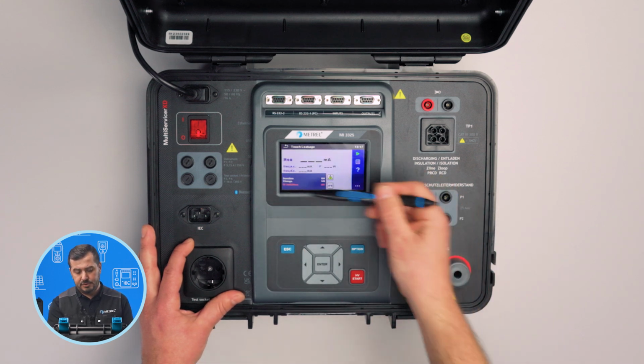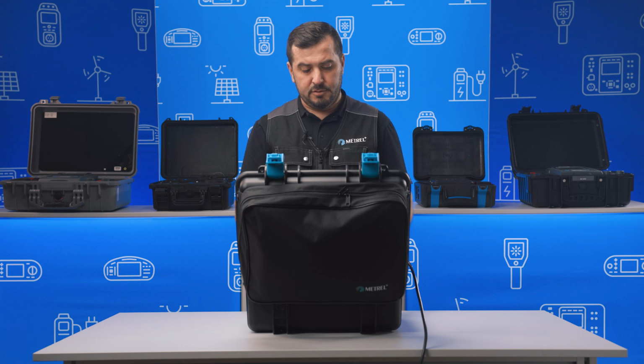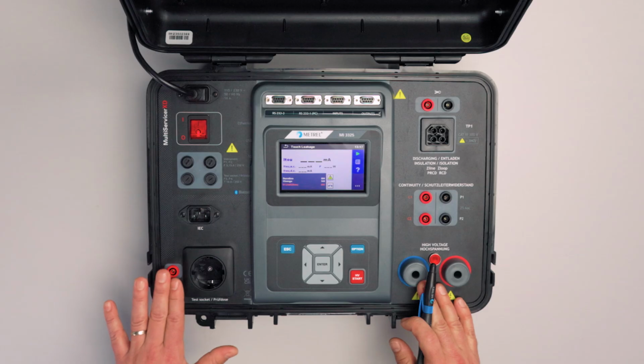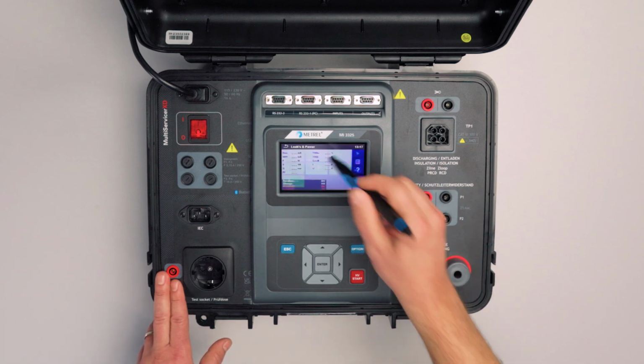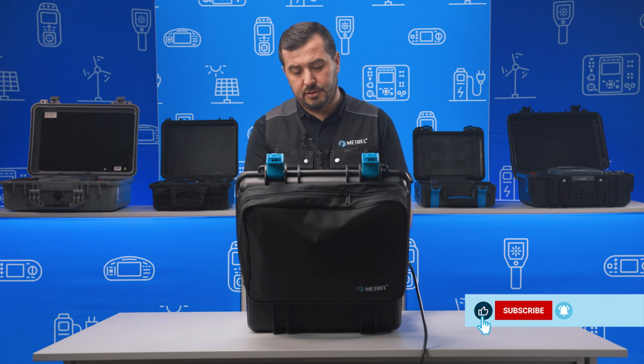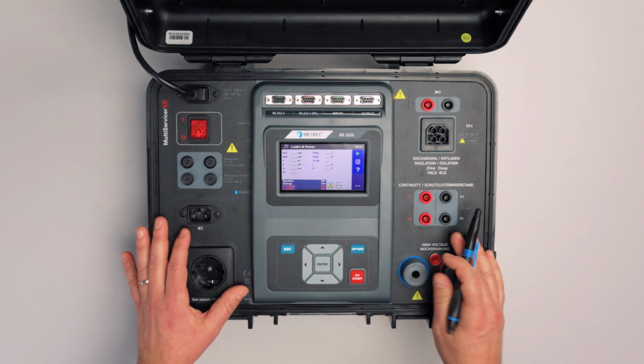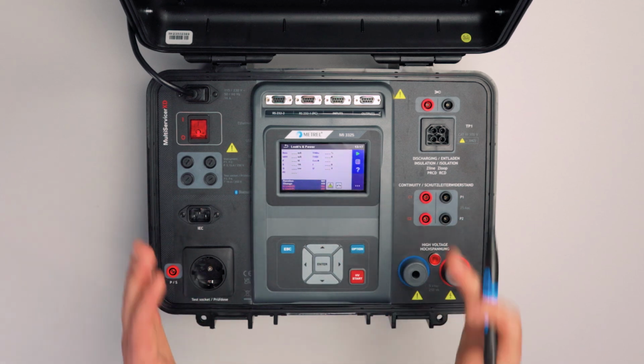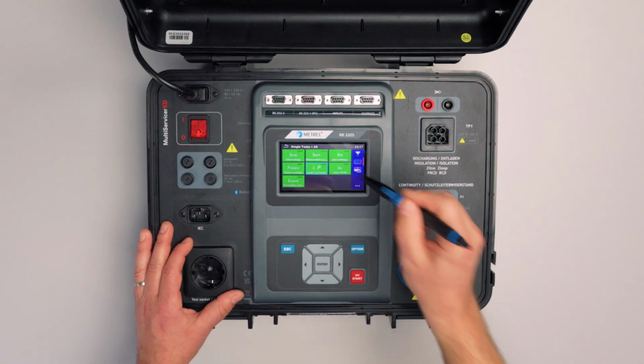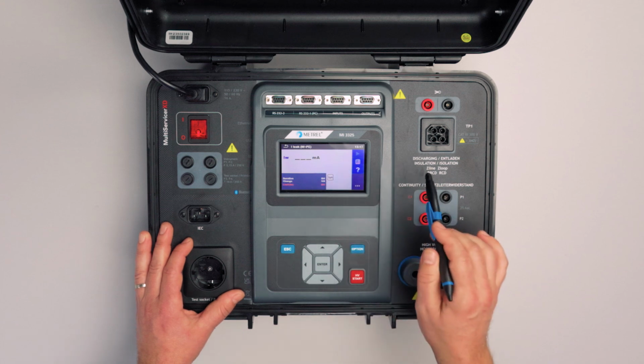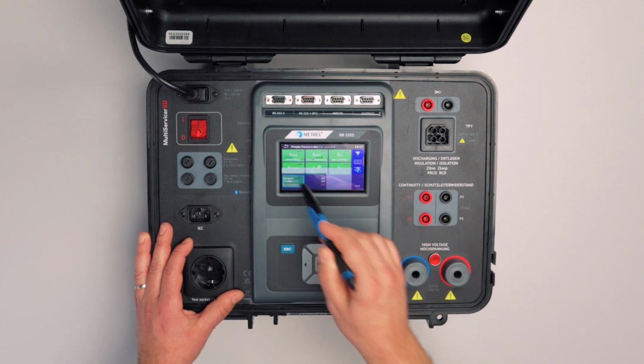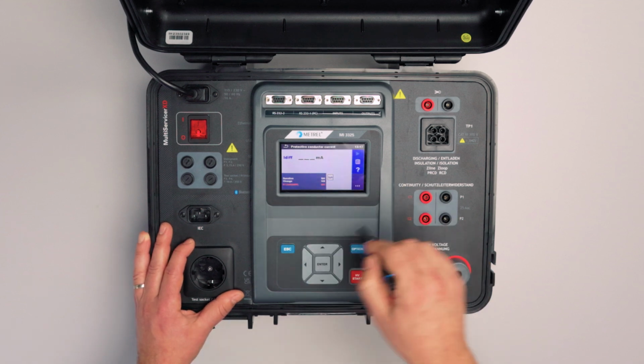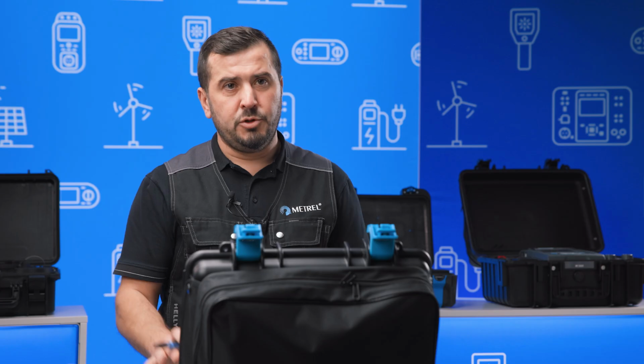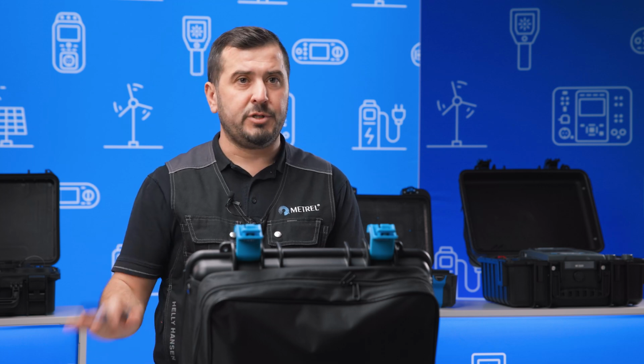Then the touch current, similar to PE leakage current, though this measurement is performed against this probe. Then a quite strong measuring function is the leakage and power. Why is it strong? Because in one measuring step we actually measure the touch current, the differential current, and also all the parameters for the power measurement. Then we have, as I mentioned, two measuring methods for testing on welding equipment, which are again supported only when we use the external active three-phase adapter.